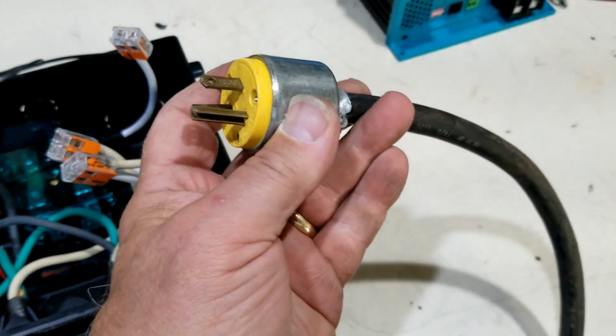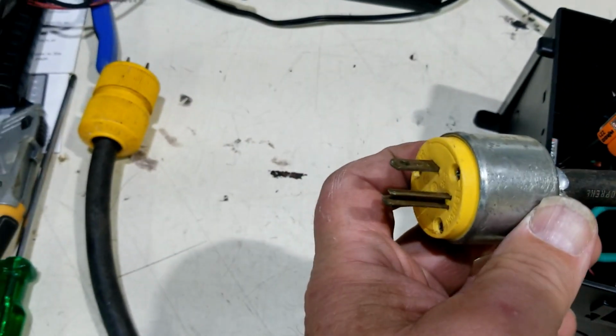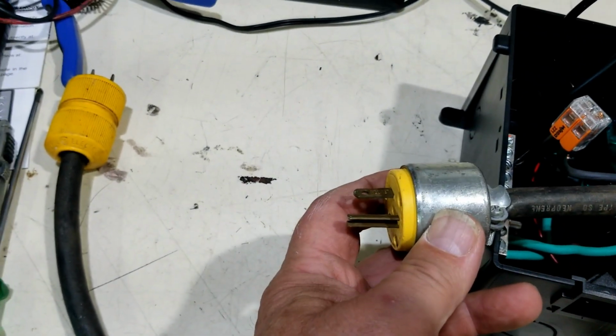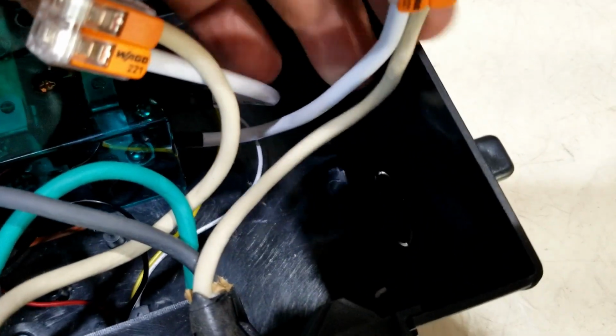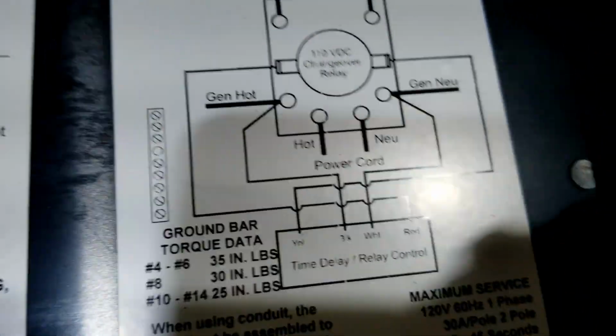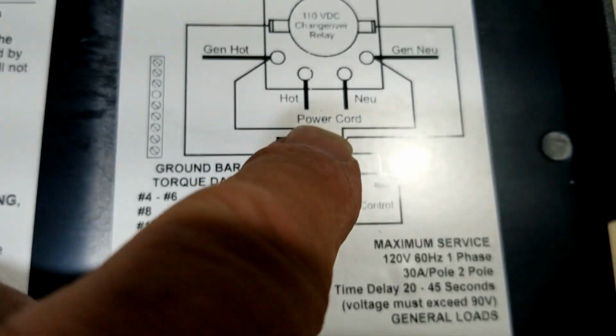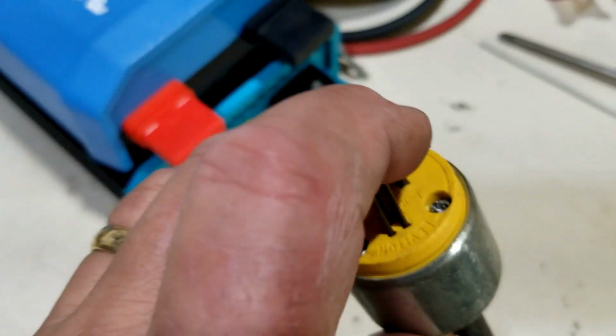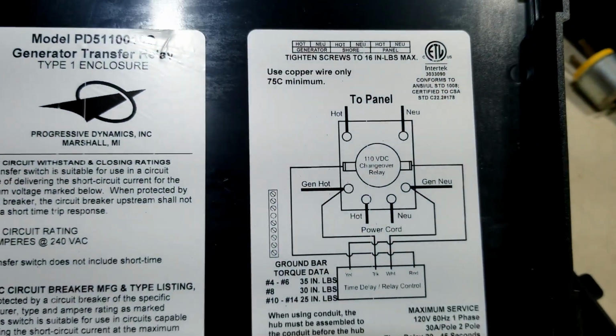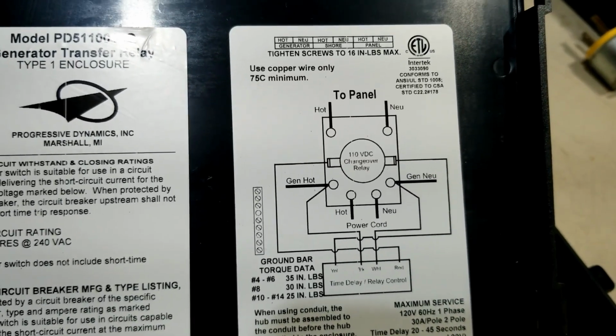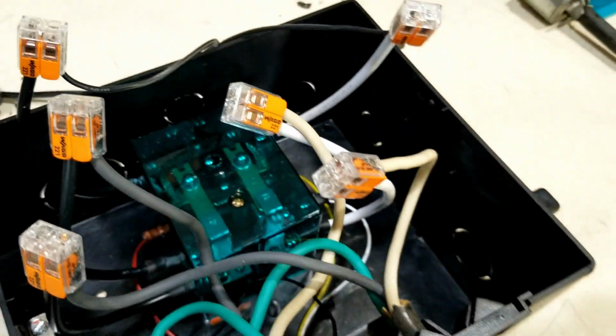I have a second plug that has, just to tell the difference, this one has the silver metallic jacket on the plug, the other one is the yellow. So the metal jacket, we can follow these lines, comes in and plugs into the automatic transfer switch on this side, which according to the instructions would be coming from our power cord. So we're going to call the metal one the power cord. We're going to call the yellow one generator, so that we can stay with the same standards as their instructions. So generator hot and neutral, and then power cord hot and neutral.